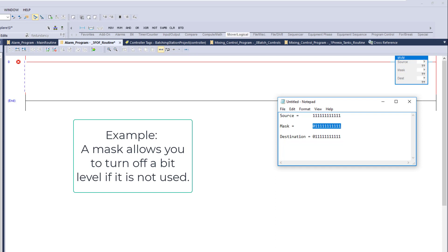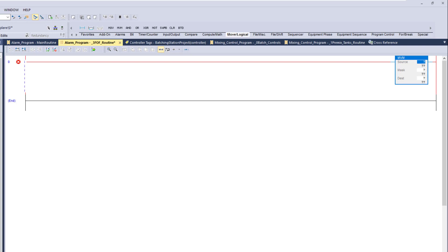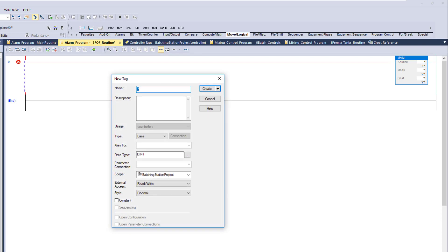90% of the time you're going to use this on a large-scale, finite number of actual alarms. In an alarming system, you can enable, disable, acknowledge, or not acknowledge specific alarms in a section — that is why a mask move is used in an alarming section.